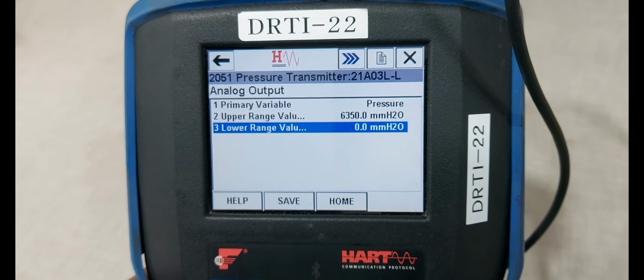Check the reference meter value. Reference meter value showing 20, both are the same. We have selected enter. Check the field device value equal to the reference meter. Now showing the same. Then press yes and enter. Okay, return to automatic mode. Then OK. Now DA trim is completed.